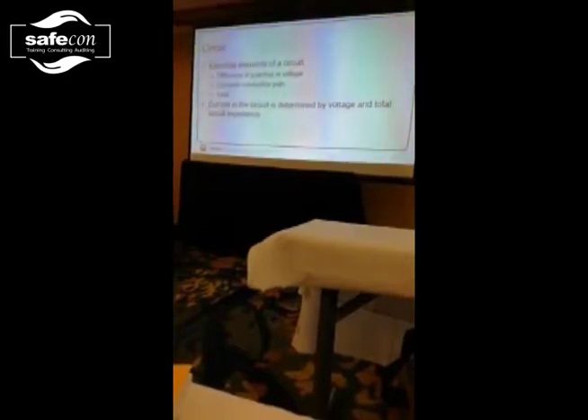So obviously, some of these I do like. Obviously, I have to have a difference in potential to create a hazard, whether it's an arc flash hazard or a shock hazard. I've got to have two sides of the circuit, or a phase to ground, or some difference in potential to make it happen. So a circuit requires a difference of potential to operate, and it completes a conductive path. The load is actually the impedance, which determines the amount of current that flows in the circuit.